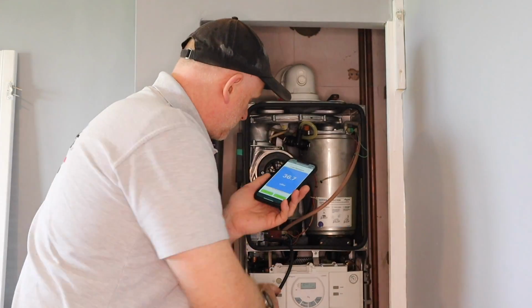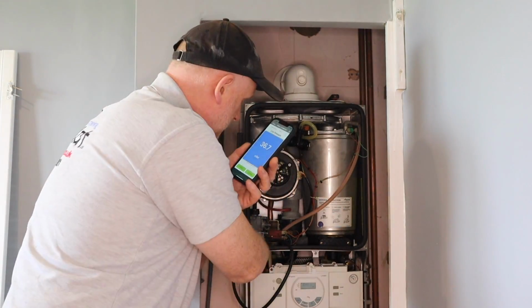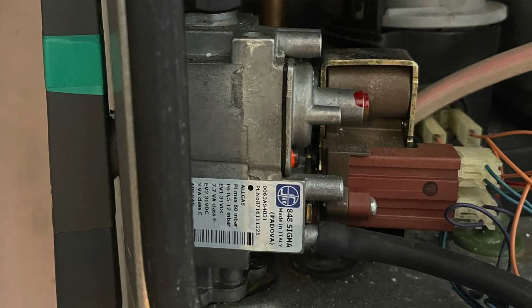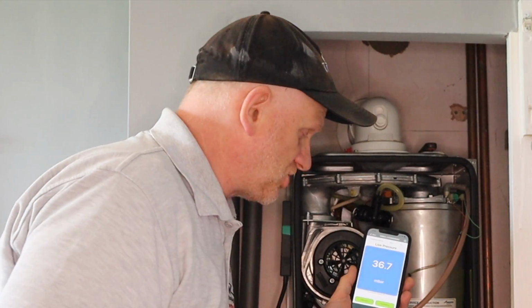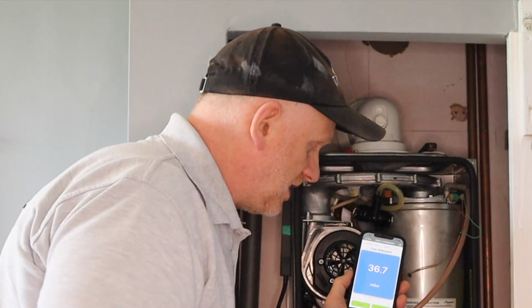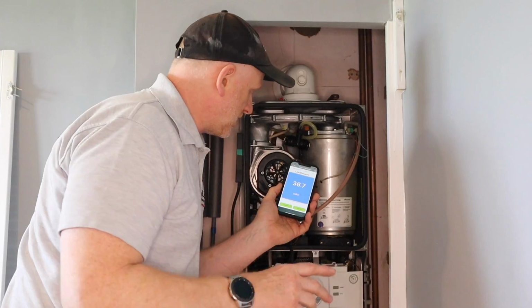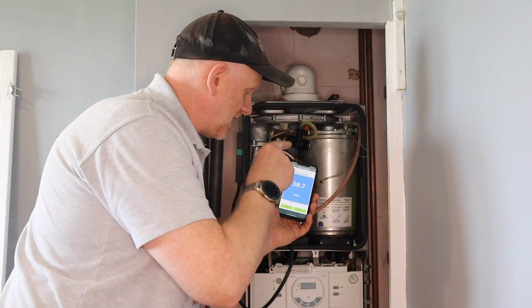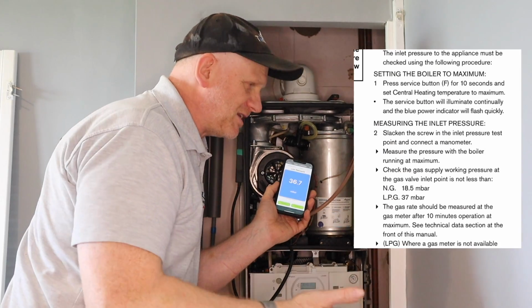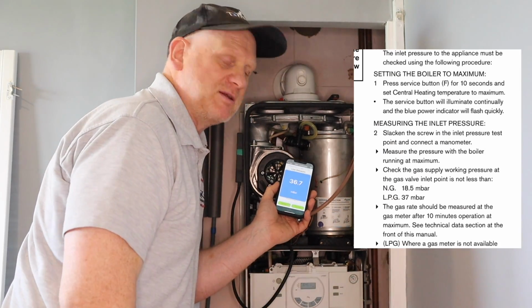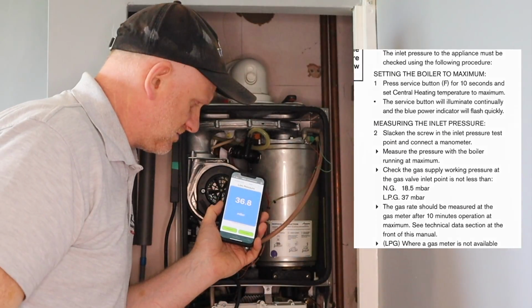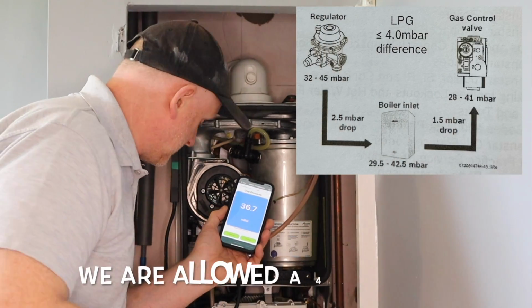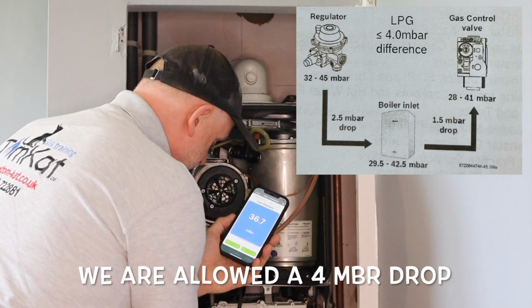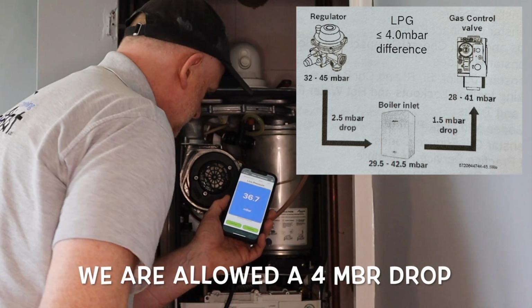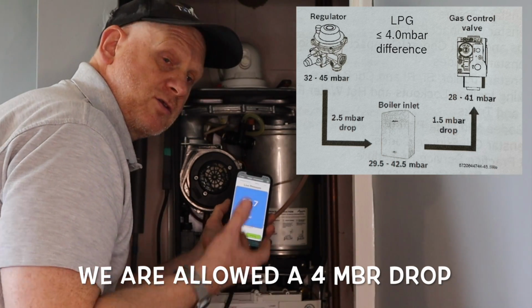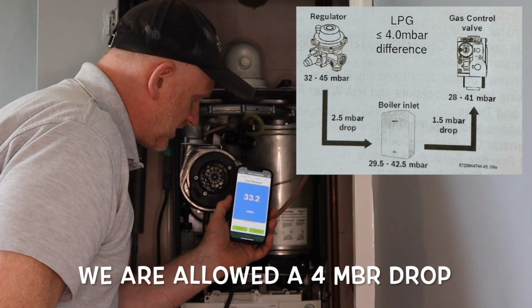So now I've connected my TPI digital manometer down here on my inlet test nipple, and it's now giving me a standing pressure of our LPG of 36.7. So again, I need to put this on maximum and see what this drops down to. Now in the book it says an inlet pressure of 37 millibars. Well, we have got an inlet pressure of just less than 37 millibars. Anyway, let's put it back into maximum again. So let's watch and see what it does when it goes into high fire.